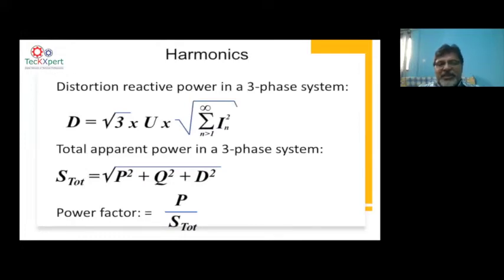Next slide. Now, when harmonics are in the system, you have a distortion power factor. This is another component of power factor that will reduce the PF of the total system. The distortion power factor is created by all the harmonics flowing in the network. √3 UI, that is the kVAR. The D stands for reactive power in kVAR. So for the reactive power in kVAR, as you all know, the equation is 1.732 into voltage into current. Now here, when there are harmonics, the current is not just your normal RMS current. It is a sum of all harmonic currents. That's why the distortion kVAR is computed based on the sum of all the harmonics. Now when you take that and bring it into the Pythagoras theorem, you see the total apparent power is a sum of the displacement and distortion components. So when harmonics are in the system, you can see the power factor goes lower than when there are no harmonics. That means harmonics can bring down your power factor. Go to the next.